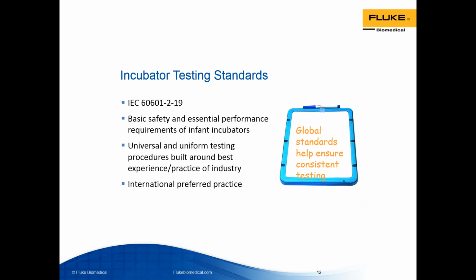So with how fragile these infants are, it becomes pretty obvious that testing all the parameters and testing them appropriately, and according to the standards and/or the manufacturer's guidelines, is absolutely critical. The International Electrotechnical Commission, or the IEC as we better know them, the IEC standards, reflect the best experience of the industry, of researchers, consumers, regulators worldwide. What the standards do is help establish a uniform and universal testing procedure for biomedical service design engineers to use, and they're critical in helping properly assess the safety of medical devices and thus ensuring patient safety.